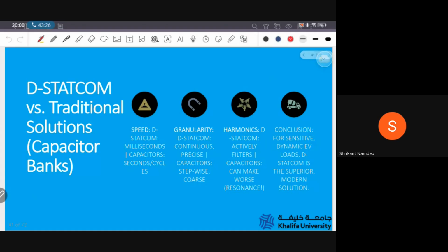Here, the STATCOM versus traditional capacitor banks. Old school capacitor banks are slow. We know we started reactive power compensation with our capacitor banks, but they are slow. And the main problem with capacitor banks is their fixed rating. When the load is fluctuating, reduced or increased, the capacitor bank rating won't change. It stays at a fixed rating, so it will either over compensate or under compensate.